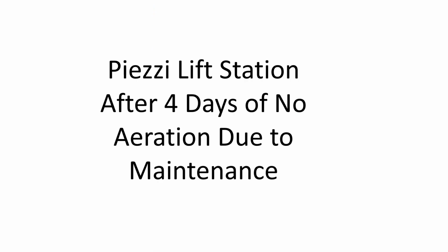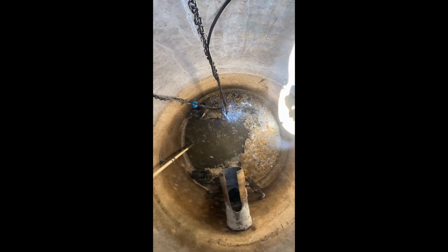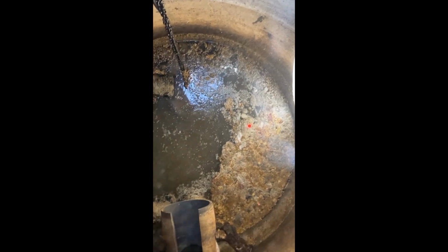During this process, we had to pause the aeration for 4 days to do maintenance, and we took a little picture of what it looked like after 4 days with no aeration. Piezzi Lift Station. This is 4 days of not running the aerator. Notice the buildup of the cap.